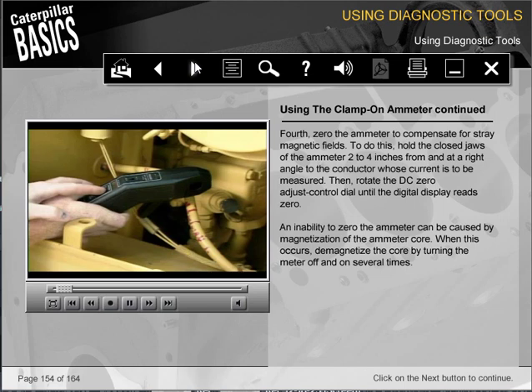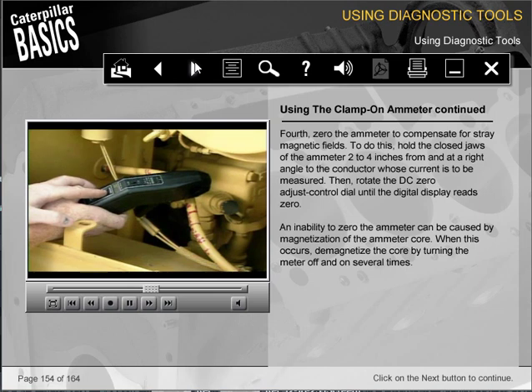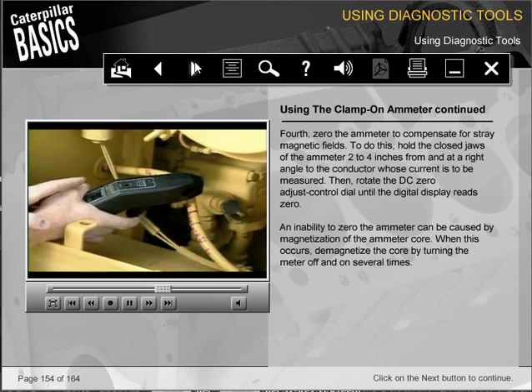Fourth, zero the ammeter to compensate for stray magnetic fields. To do this, hold the closed jaws of the ammeter 2 to 4 inches from and at a right angle to the conductor whose current is to be measured. Then rotate the DC zero adjust control dial until the digital display reads 0. An inability to zero the ammeter can be caused by magnetization of the ammeter core. When this occurs, demagnetize the core by turning the meter off and on several times.